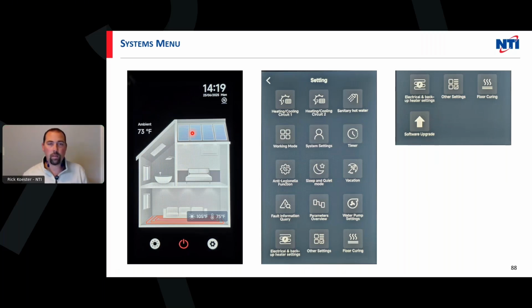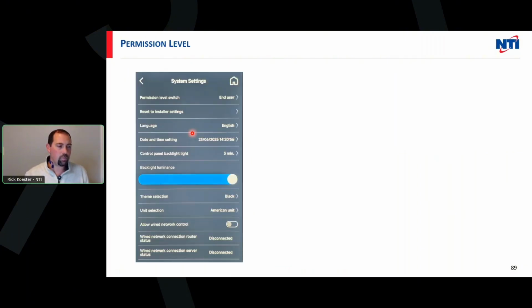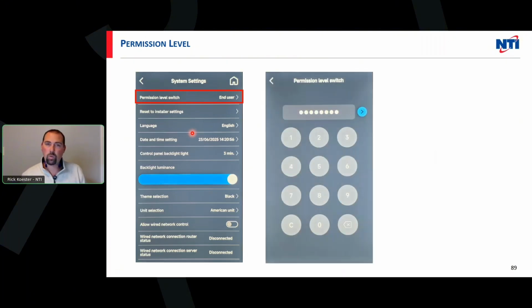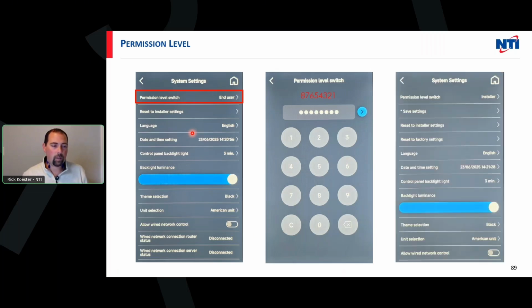In order for me to adjust any parameters, I first have to get in as an installer. If I hit the system settings button, at the top of the page it says permission level switch. So I'm going to go from an end user to an installer. I click on that, and it brings up my password screen. The password is counting down from 8 to 1. Hit the little blue arrow on the right, and then I can confirm at the top of the screen that it has switched and we are now an installer. That's going to expand a lot of those menus.